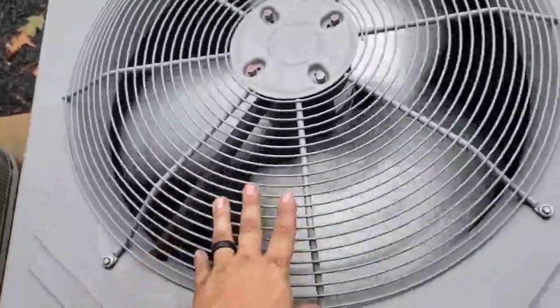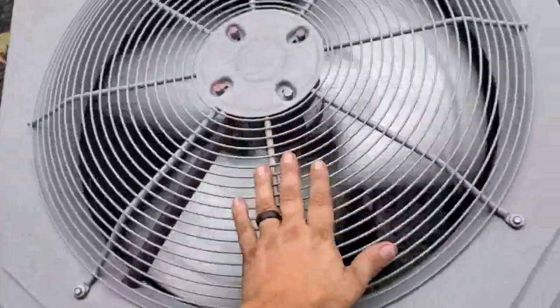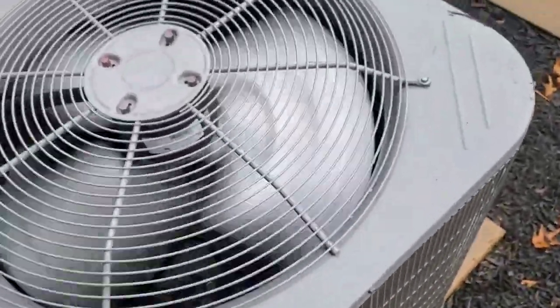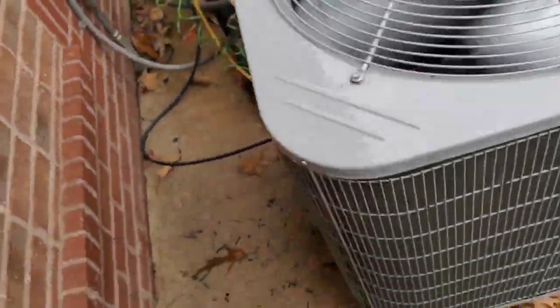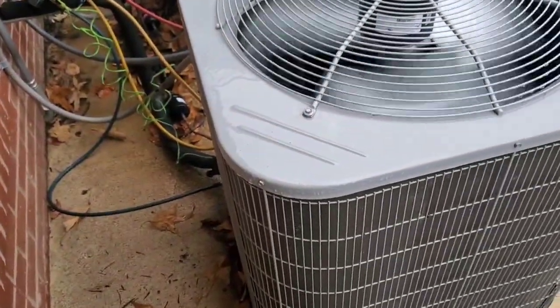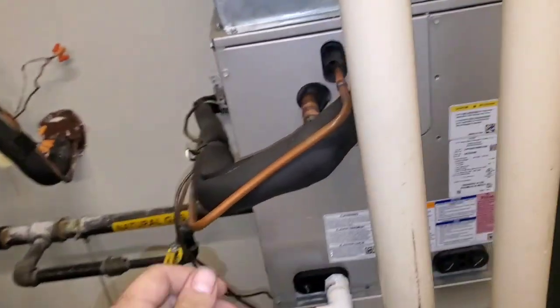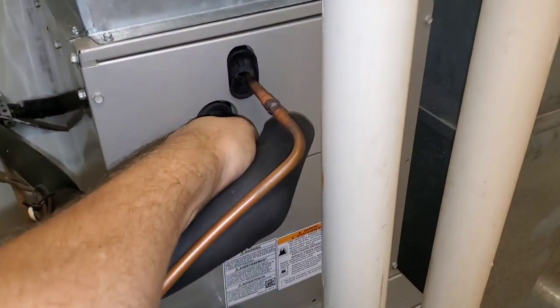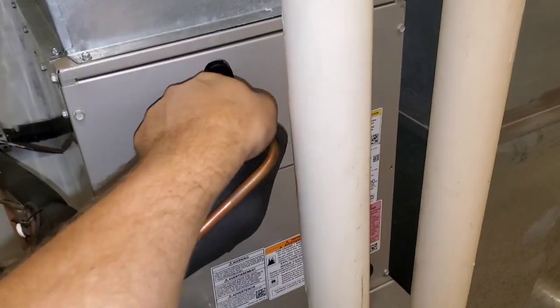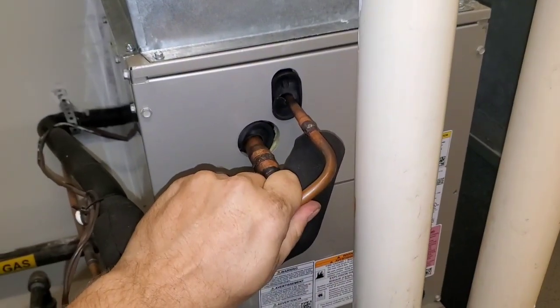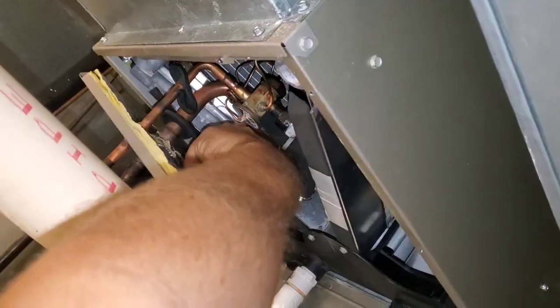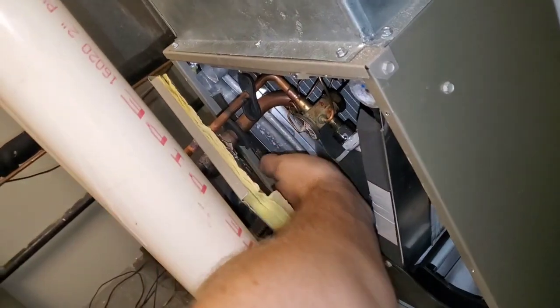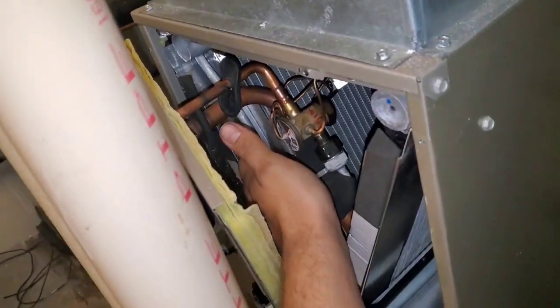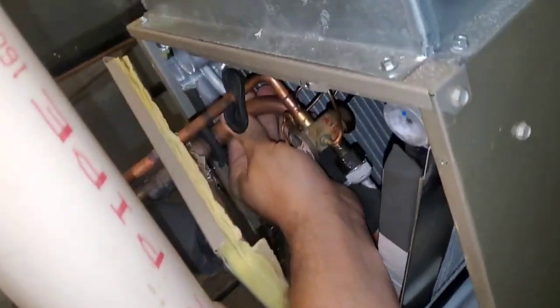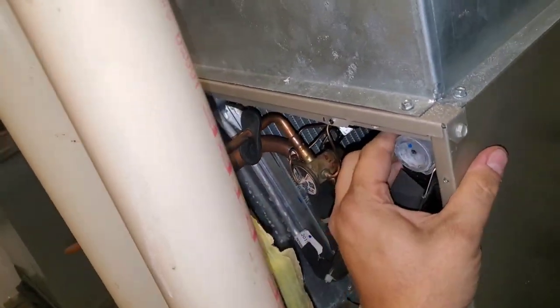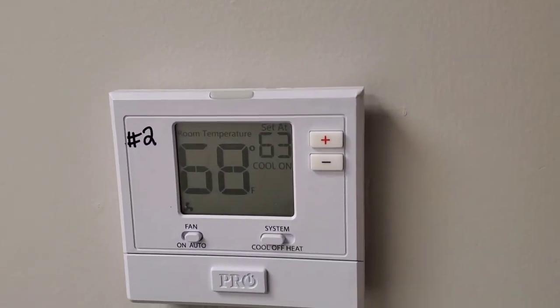6 years old. No older than that. More likely it's like 5 years old. You know, the equipment's a year or two old when you get it. Back up here at the furnace, and it feels right. This line is ice cold. I don't feel no flash gas in the liquid line anymore. Line here is getting below freezing. It's got a little bit of frost on it. Suction line is not freezing. Yeah, the evaporator's kind of cool. 68.